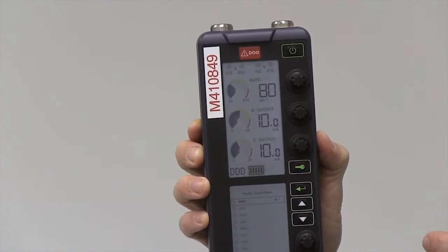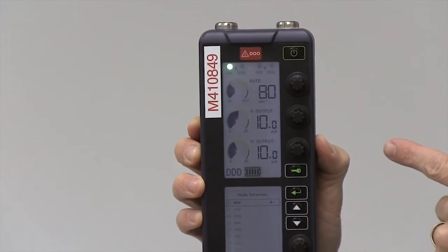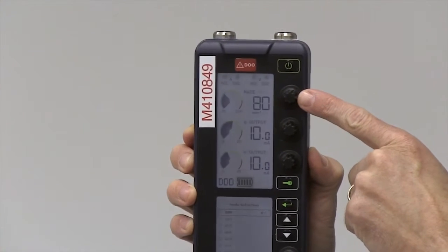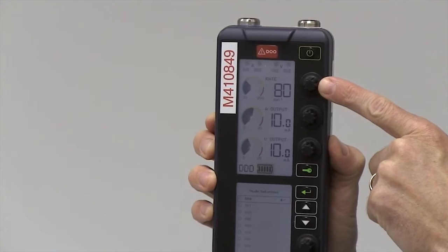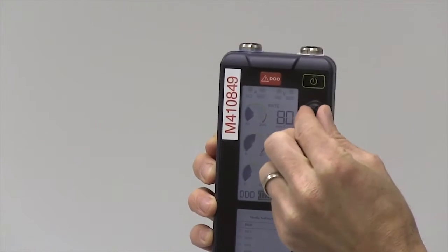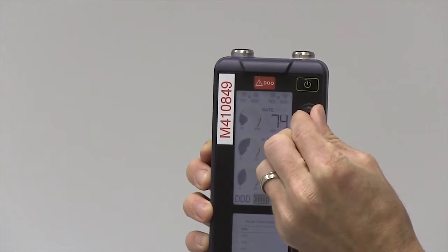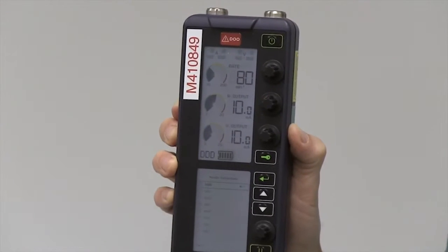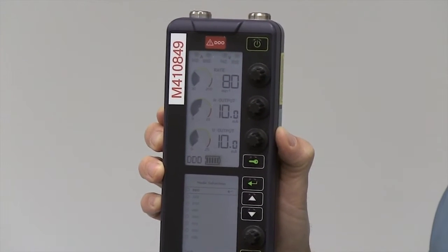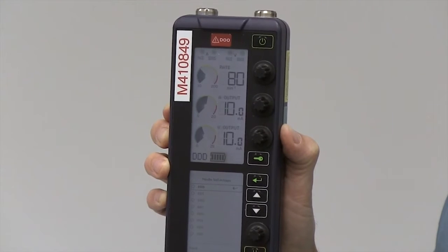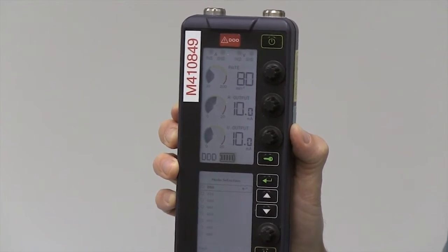You're going to notice 3 dials on the top half of the pacemaker generator. The first one deals with the rate of the pacemaker generator. It can be decreased or increased as needed. I would suggest setting the rate of the pacemaker higher than the patient's underlying rhythm if you're treating a bradydysrhythmia.